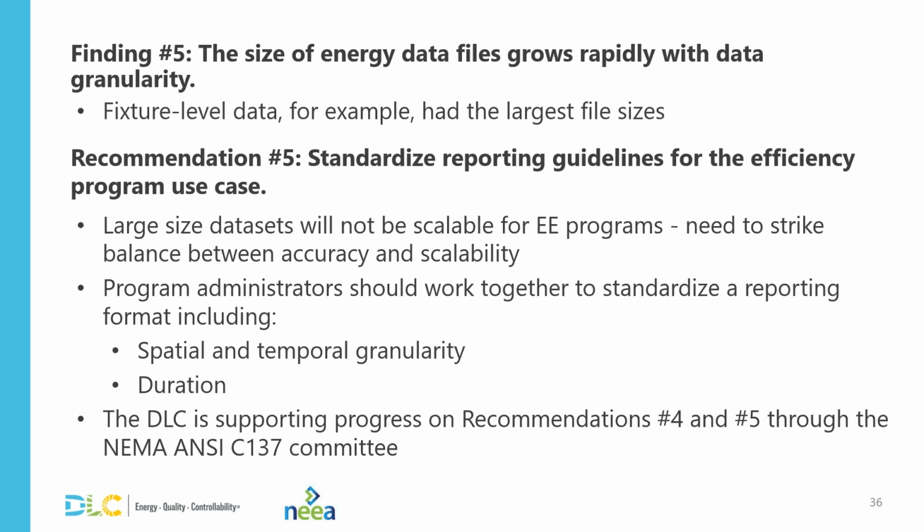The size of NLC energy data grows rapidly as the spatial and temporal granularities increase. For instance, a data set reported at the building level for 2 weeks at 15-minute intervals could be as small as a few hundred kilobytes, and in contrast, a data set at the fixture level for 6 months at a 5-minute interval could easily be several gigabytes. Even in this study, this discouraged some contributors from providing the most granular data. This suggests that it would not be a scalable model for efficiency programs to require the most granular energy data.